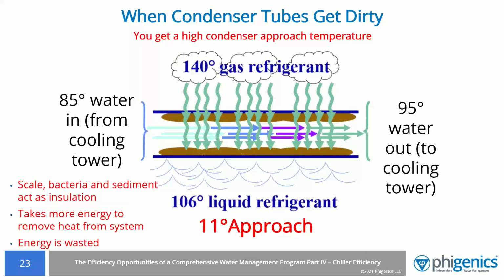We're seeing a lot more microbiological fouling than we used to see many years ago, when we had different treatment processes. And as that fouling builds up in the tube, the refrigerant temperatures have to go higher in order to force that heat out through the tube, through the scale, into the water. That raises the refrigerant pressure. As the pressure goes up, energy goes up, efficiency goes down, cost goes up. So you want to make sure that you're keeping those tubes as clean as you can, identifying if there's fouling, and correcting it in a timely manner so that you don't waste a lot of energy.